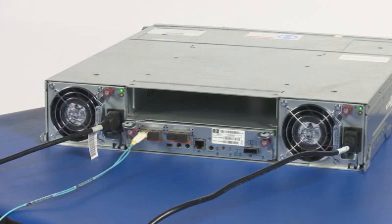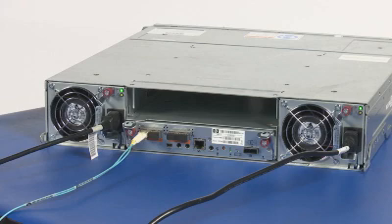In a single controller configuration, if transporting the compact flash to a new controller, remove the controller only after the cache is copied to the compact flash. When the copy is complete, the cache status LED is off or it is flashing one-tenth of a second on and nine-tenths of a second off.